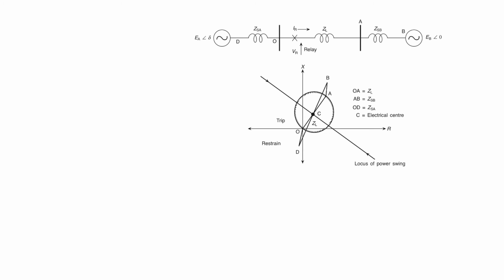Now the performance during the power swing. The Mho relay occupies a much smaller area in the RX plane, as you have seen. To that extent it is more immune to power swing. However, when the swing is very large, the impedance seen enters into the circle, and then the relay trips. Special relays known as blinders can be used to prevent maloperation during the power swing.